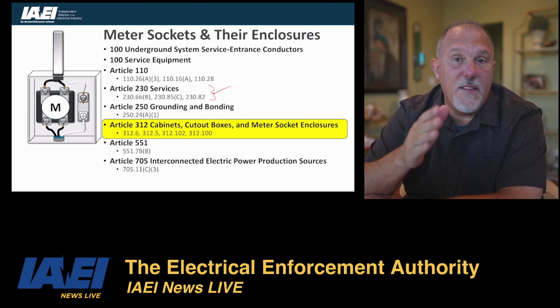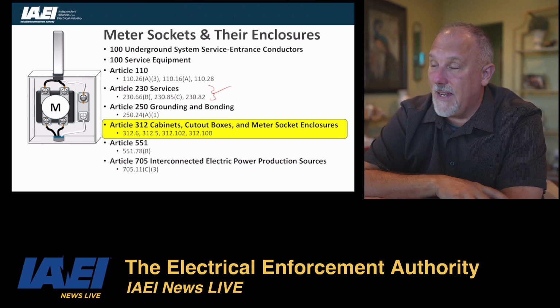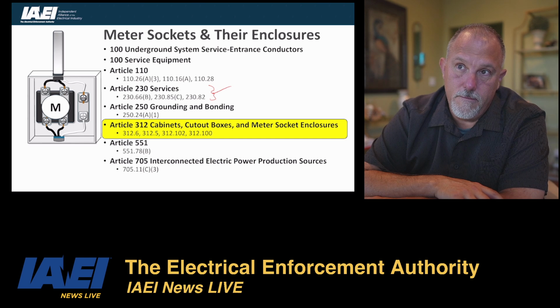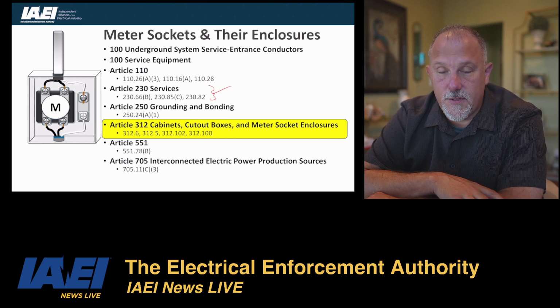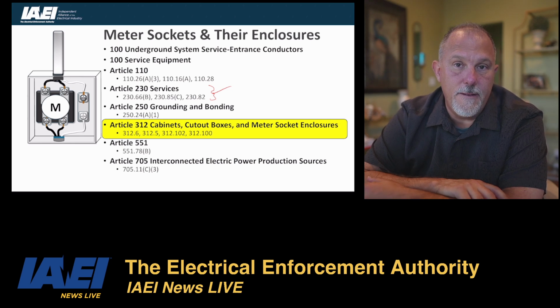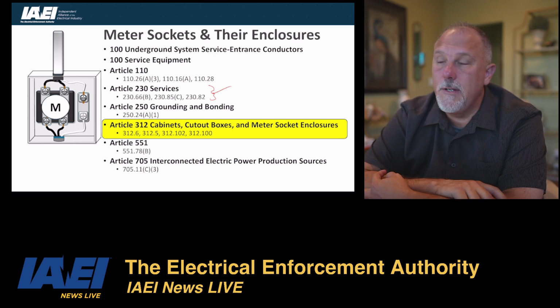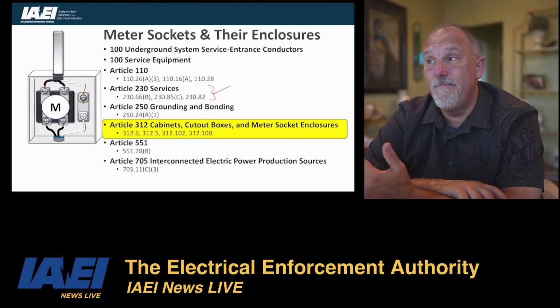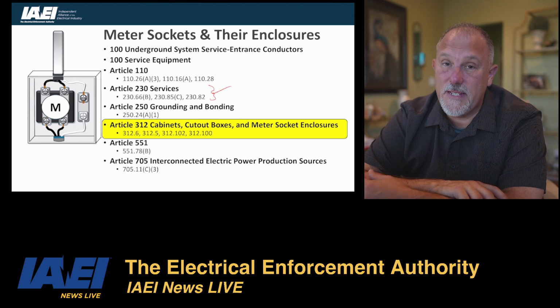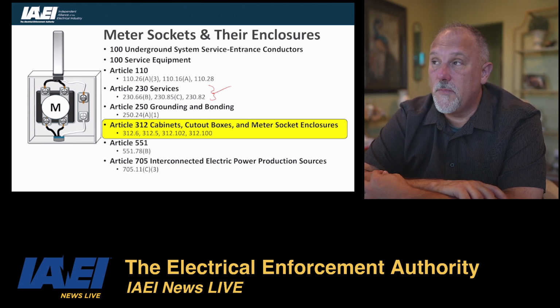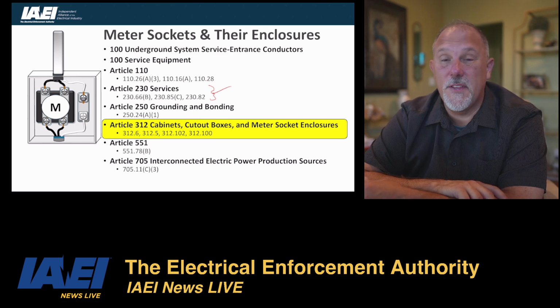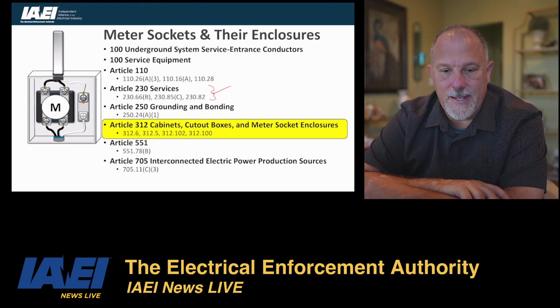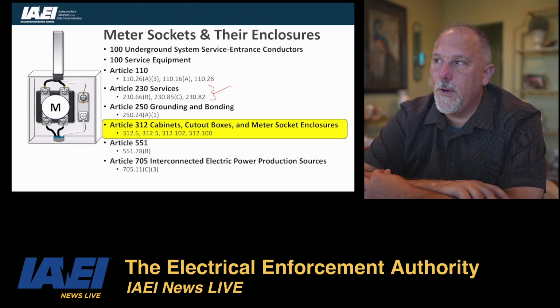But even if it's inside, and you're putting the transfer switch in between the utility and that main panel board, which used to be your service panel board and now is a feeder panel board, you now have a new service equipment. So I would say you're replacing that service equipment with something new, a new service equipment which is a transfer switch. And then you're going to need to put a disconnect outside.